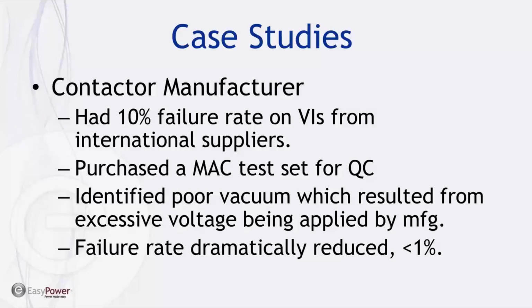So they reached out to us about our MAC test set because they had suspicions that it was related to the vacuum level inside. So they purchased a MAC test set and put it into their QC program, and they identified approximately 10% of these vacuum interrupters that they were receiving were at a very high pressure near failure when they were receiving them from overseas.